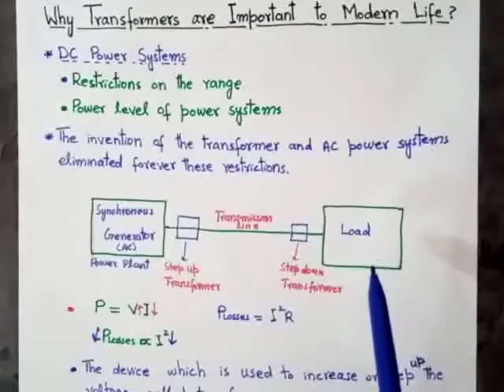So if we increase the voltages 10 times for the same amount of power, then the current will reduce 10 times as well, and the losses will reduce 100 times. If the current reduces 10 times, the losses reduce 100 times, because the relationship between losses and the square of the current is directly proportional.